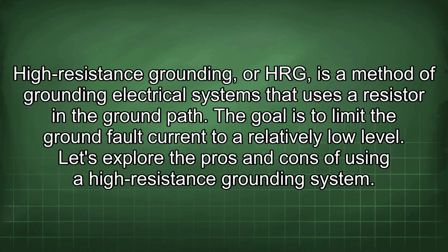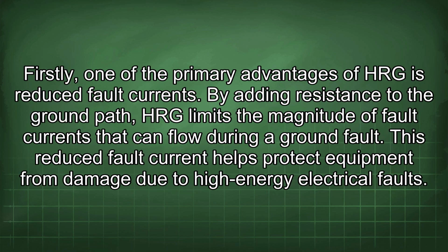High resistance grounding, or HRG, is a method of grounding electrical systems that uses a resistor in the ground path. The goal is to limit the ground fault current to a relatively low level. Let's explore the pros and cons of using a high resistance grounding system. Firstly, one of the primary advantages of HRG is reduced fault currents.